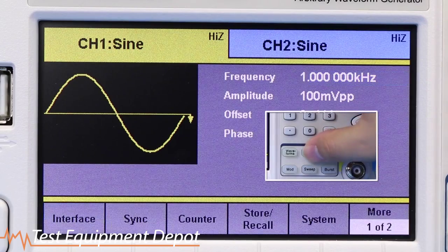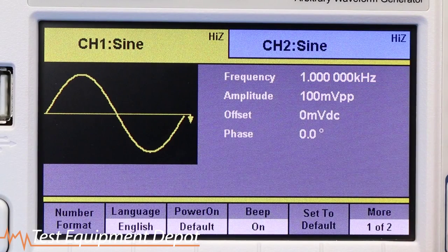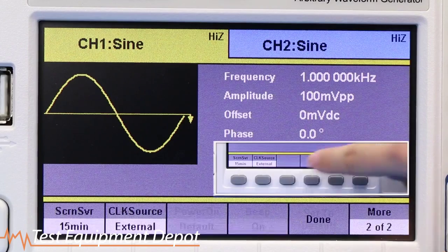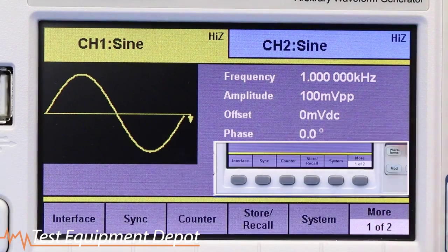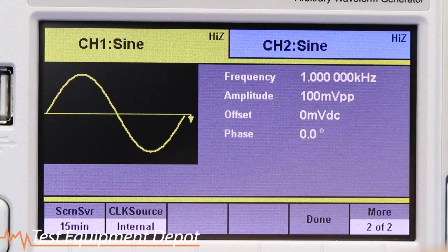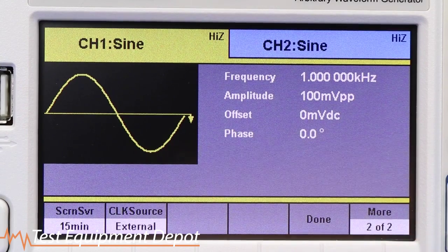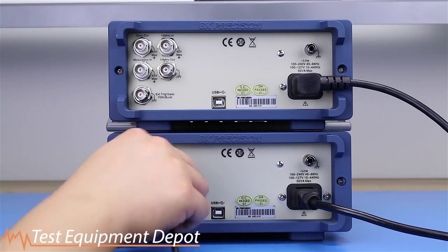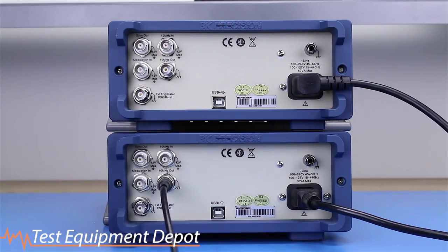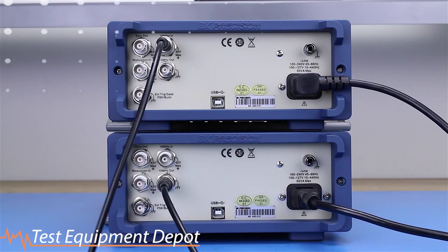Press Utility, System, Clock Source. On unit 2, set clock source to external. Connect the 10 MHz out BNC connector on unit 1 to the 10 MHz input BNC on unit 2.